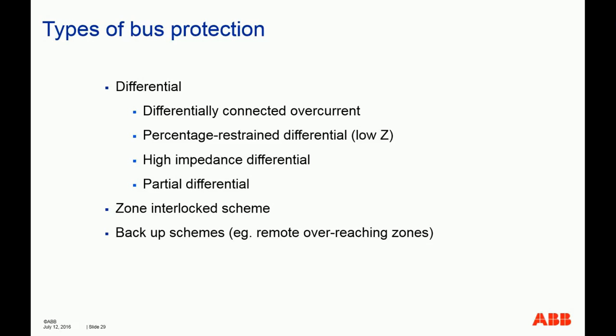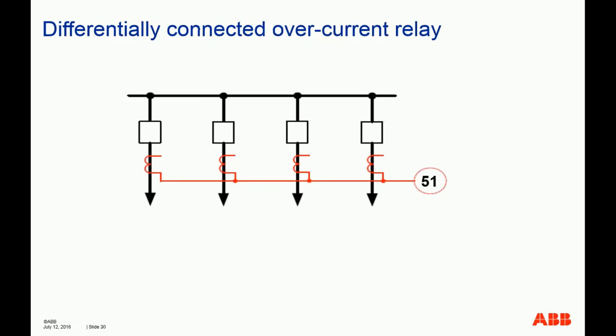First of all is the differential. Most bus protection schemes we see nowadays are differential. Starting with the most simple, the differentially connected overcurrent, to the legacy percentage restraint differential, to the still very commonplace high impedance differential, partial differential, and also the numerical differential relays that we see very widely nowadays. And then we will introduce the zone interlock scheme and some backup schemes.